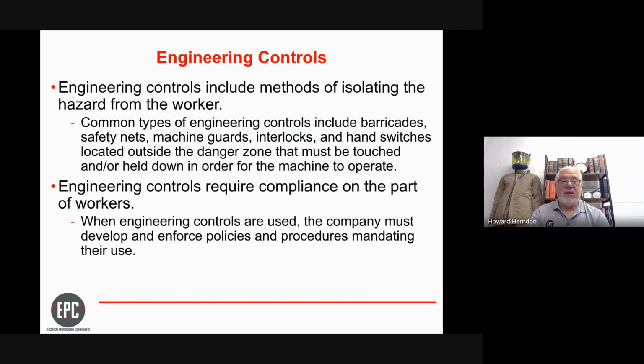But the worker has to be in compliance with this. If I open a cabinet and it has a limit switch that shuts the power off, yeah, that's great to de-energize the system. But many times we find that door switch or interlock gets wired closed, or has tape around it. Well, that doesn't do anything to help isolate the worker from the hazard.